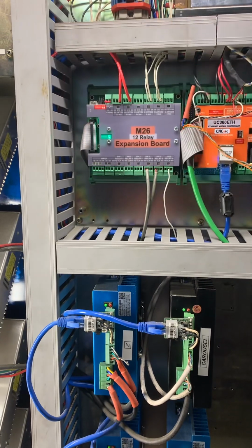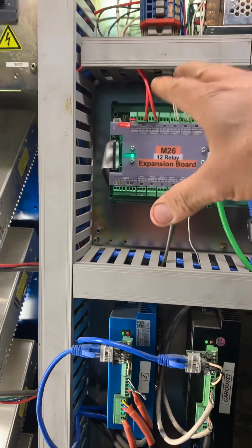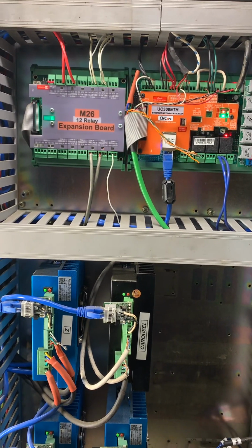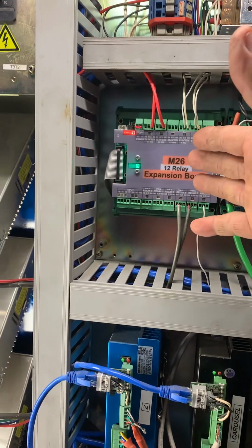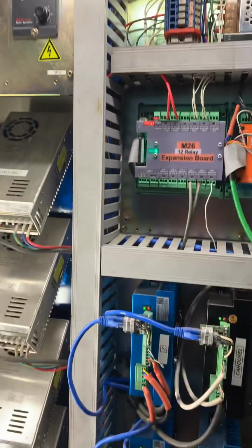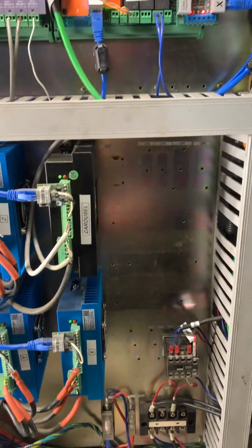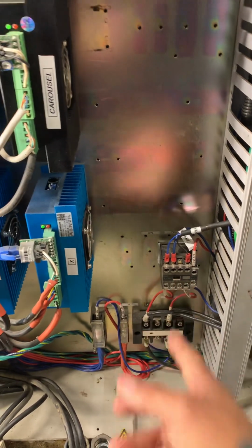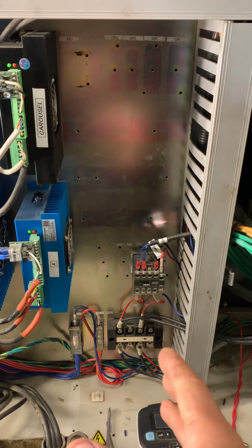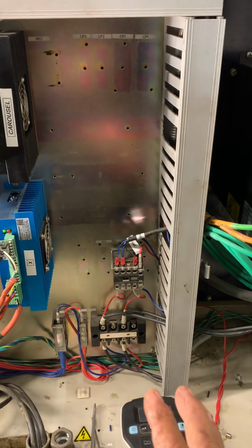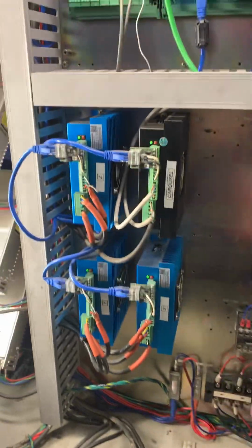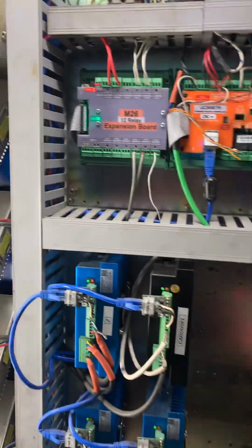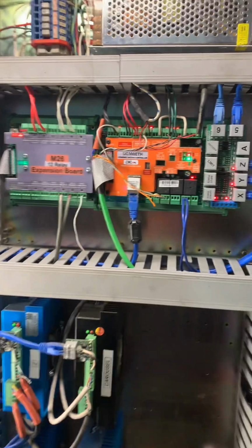The way I like to do it is I always try to get ground into the relays. I think it's called sinking or sourcing, either one of them. I don't remember now which one. In this case I'm getting ground to the relay, and the relay is just sending ground over to the fans. And my power is coming from my contactor. So anytime you hit the e-stop, your emergency stop, it will kill the whole powering of your relay. So you're not going to have 110 volts or 220 volts feedback through the coil of the fan into the relay. So if I hit my e-stop, I can still work on it and not get shocked by the power.